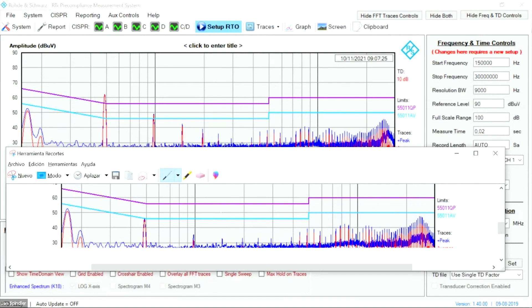This is very easy to test: take the filter and put it outside of the product. The filter outside the product is able to comply with regulation. When the filter is inside the product, you fail — you increase by 5, 10, or 12 dB. The position of the filter in your product matters enormously, especially if the filter is close to heat sinks with strong dV/dt from power electronics circuits, or close to magnetic field sources like the inductor in a buck converter.